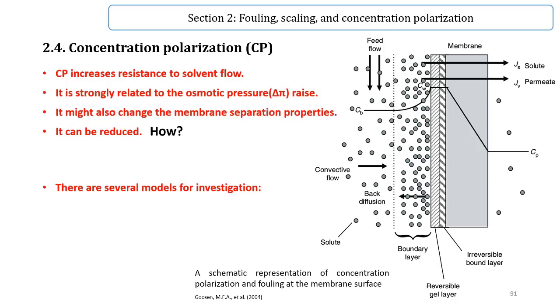Concentration Polarization. The pressure-driven fluid flow through a selective membrane convectively transports solute towards the membrane surface. The partially or totally retained solutes will accumulate in a thin layer adjacent to the membrane surface, generating a concentration gradient — that is to say, the solute concentration near the membrane surface is much higher than that of the bulk feed solution.